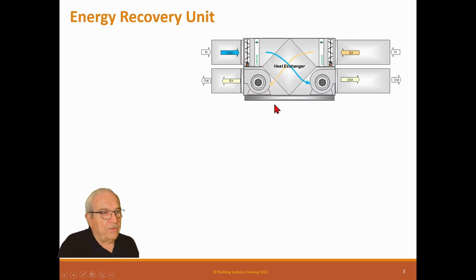Okay, energy recovery units. These are simple systems that have heat exchangers inside them. It could be a heat wheel or it could be a heat exchanger. And basically what happens is the exhaust air comes out, goes through the unit this direction and is exhausted, and the outside air comes in this side, goes to the heat exchanger and goes to the building as makeup air. So the way these work, you'll notice there's filters and dampers. These are isolation dampers to isolate the exhaust stream from the building and isolate the fresh air system from the building. And they have filters on both sides.